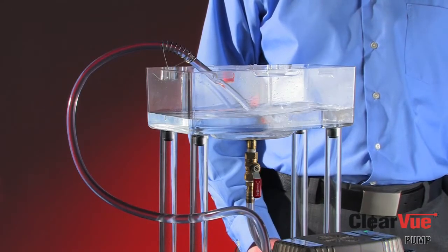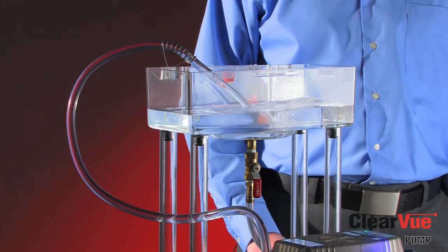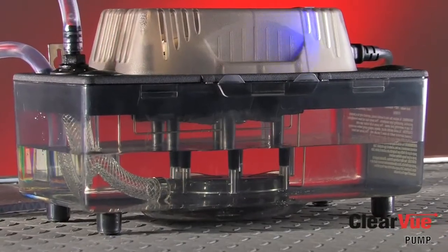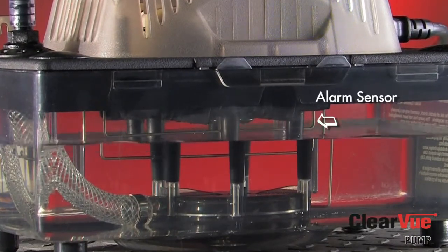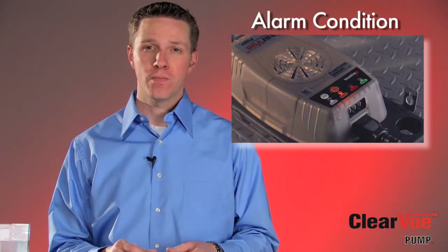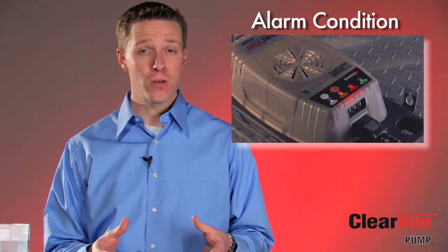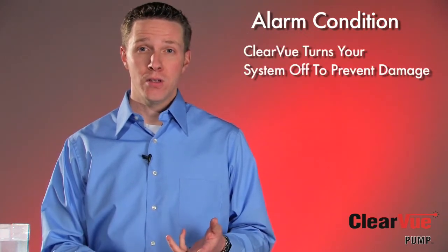If the water continues to rise and hit the run sensor, ClearVue will just continue to ramp that motor up to full speed. If the water continues to rise to the high-level sensor, ClearVue will go into an alarm condition. I'll block off the drain line here to simulate a clog or a kink. Since we've blocked the line, the water will continue to rise until it hits the high-level alarm sensor. Now that it's hit the high-level alarm sensor, it's engaged the alarm cycle. While ClearVue is in an alarm condition, ClearVue — if it's wired into your control circuit — has shut off the compressor, which will prevent an overflow condition or damage to its surroundings.